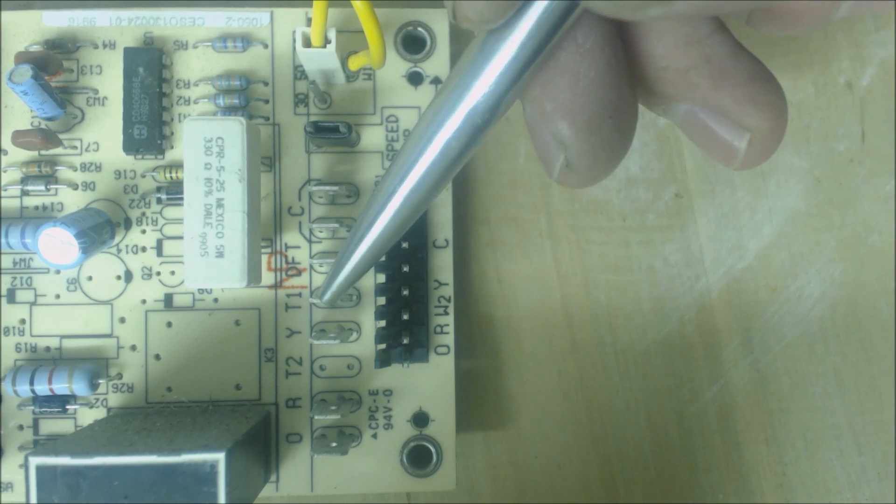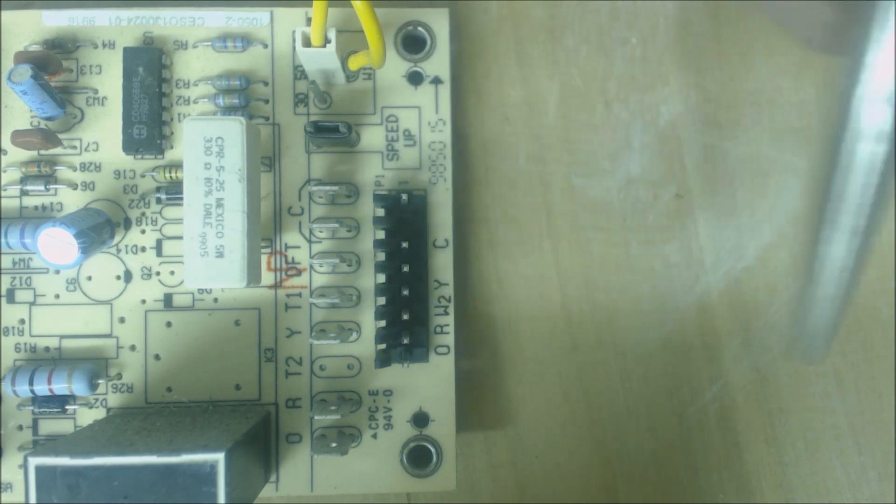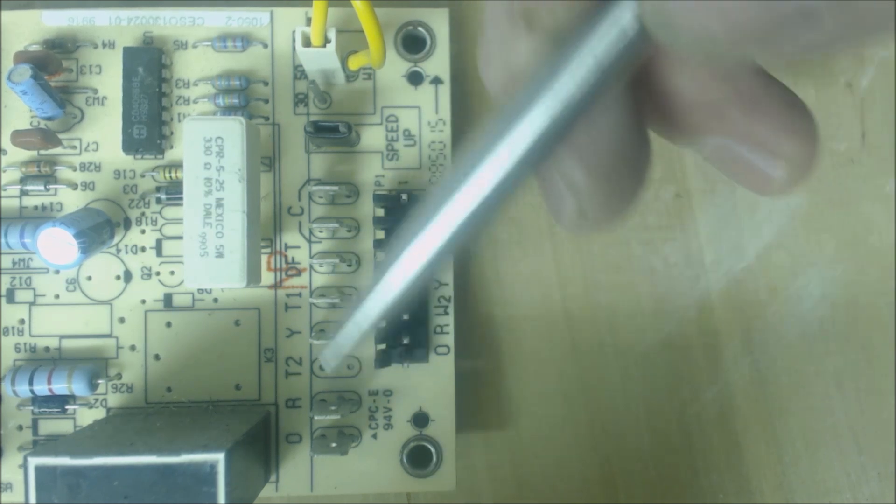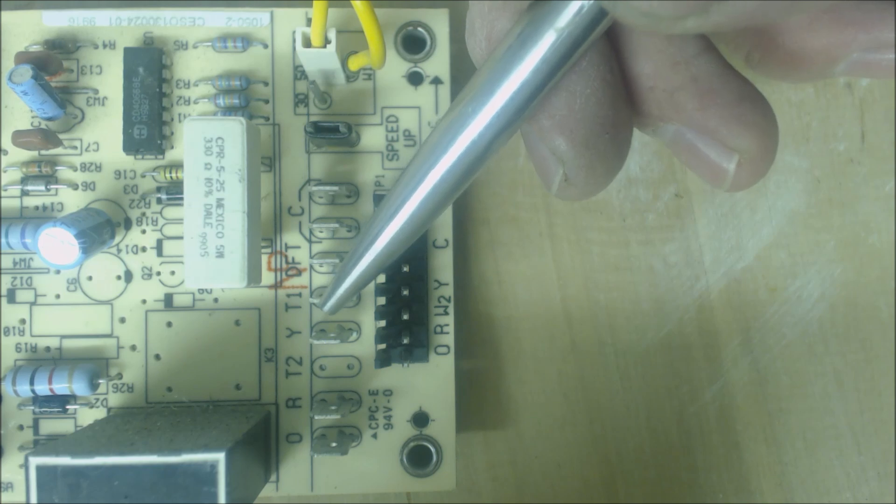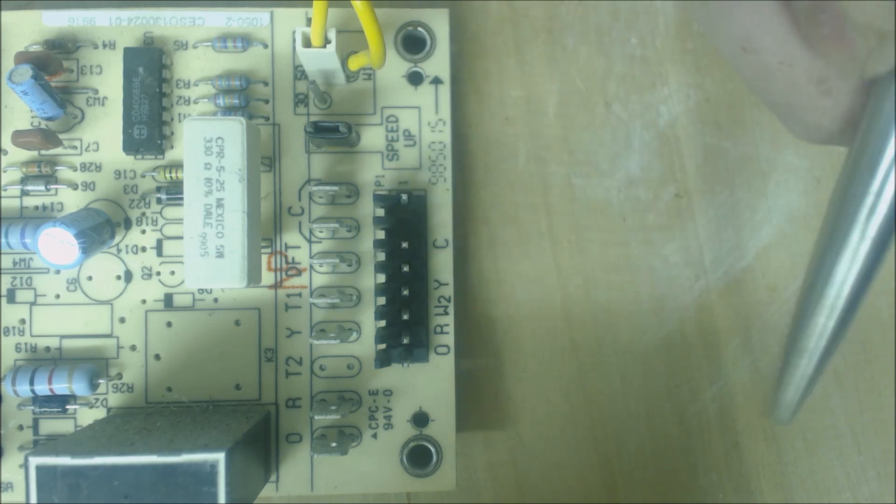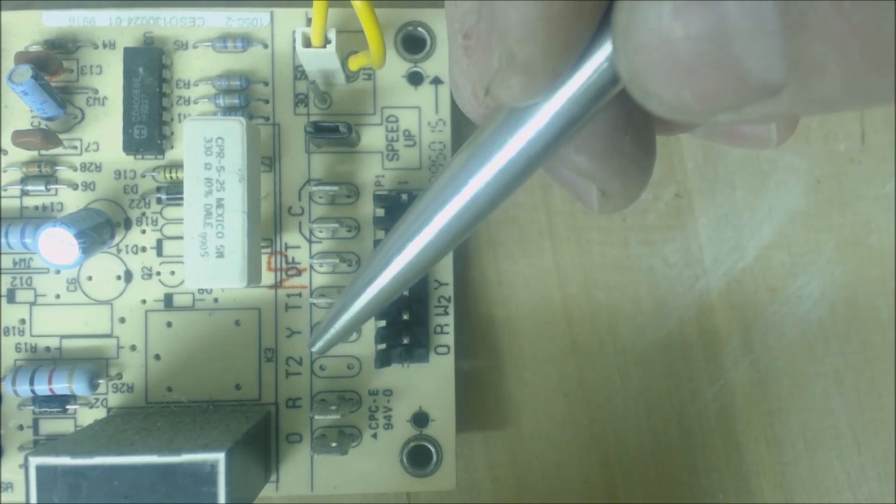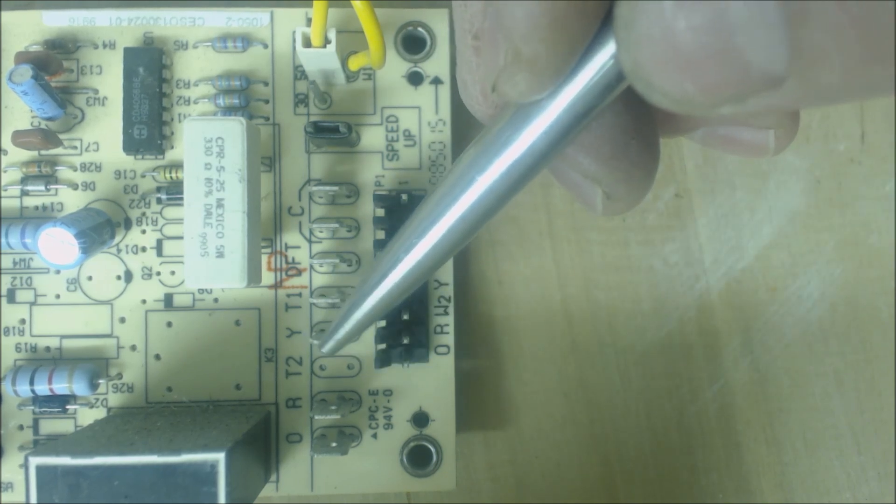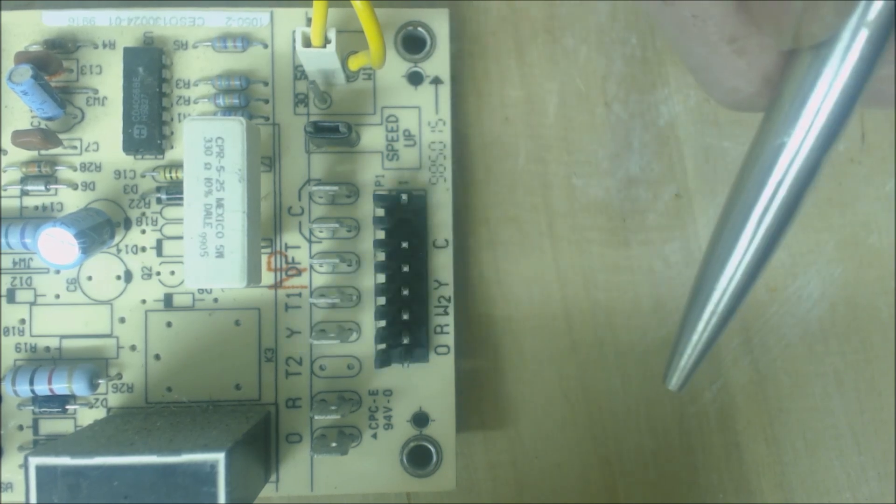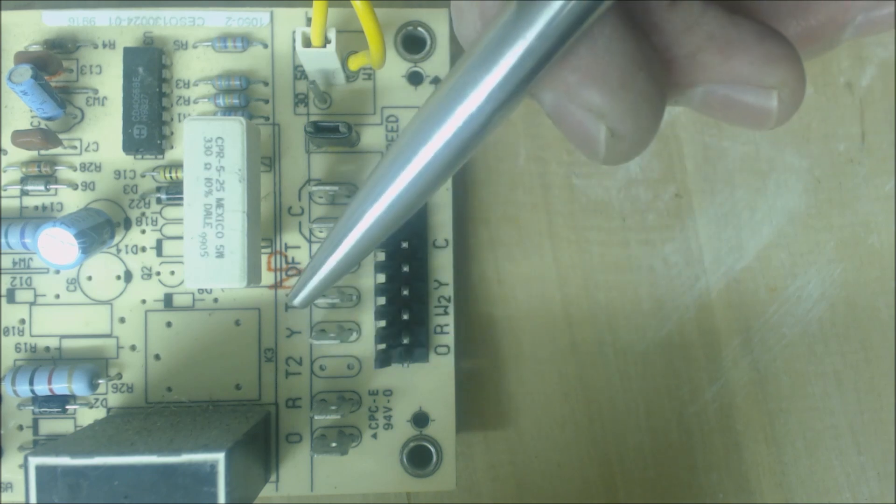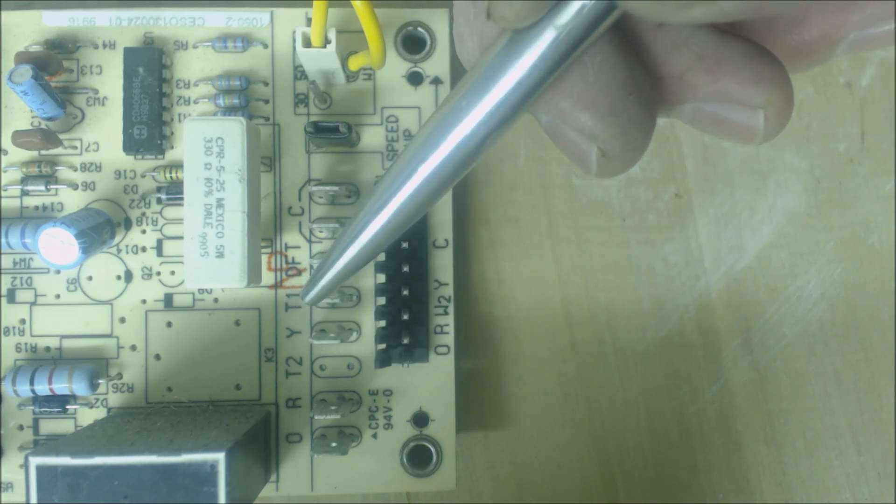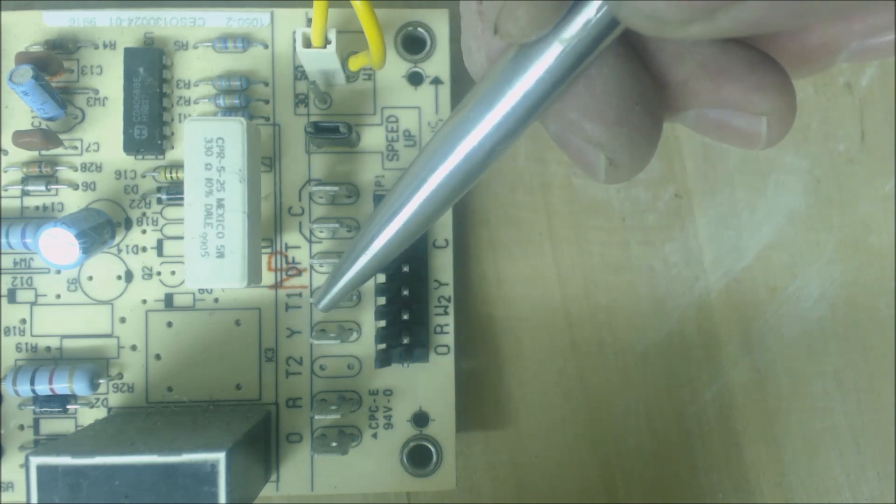You normally have a wire coming back from all those pressure temperature limit switches to T1, and then you have power coming off of T1 to the contactor. Those two wires could also meet on the contactor and just provide 24 volts back to T1 over here. But it starts here at Y, goes through the pressure temperature safety switches, and ends up at the contactor and T1.